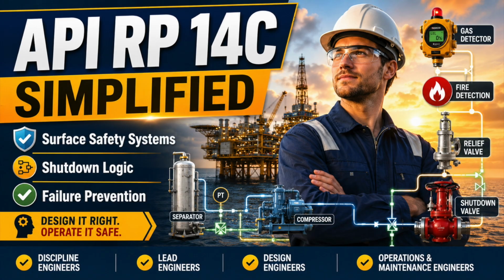These set points are dynamic. They are not decorative marks on a vessel drawing. A perfectly calibrated level switch at the wrong elevation is still failed protection.